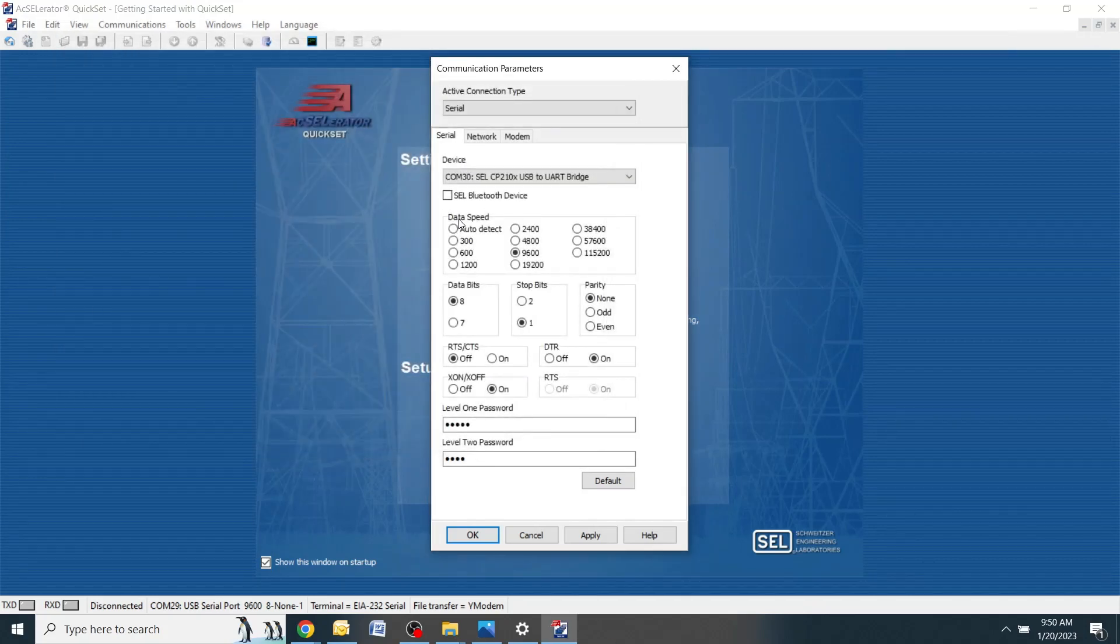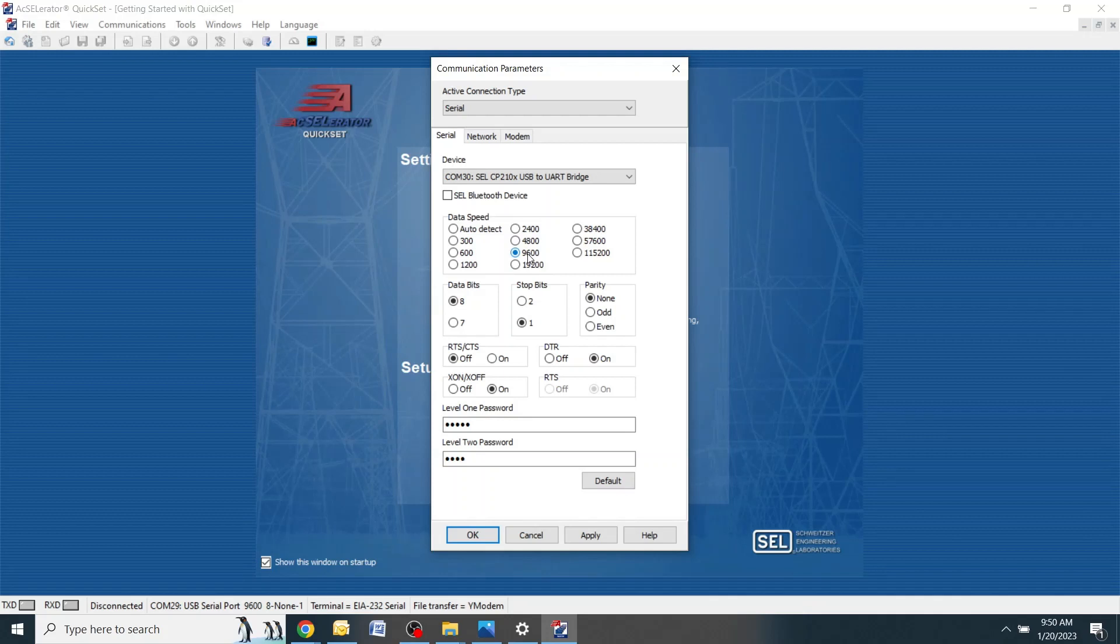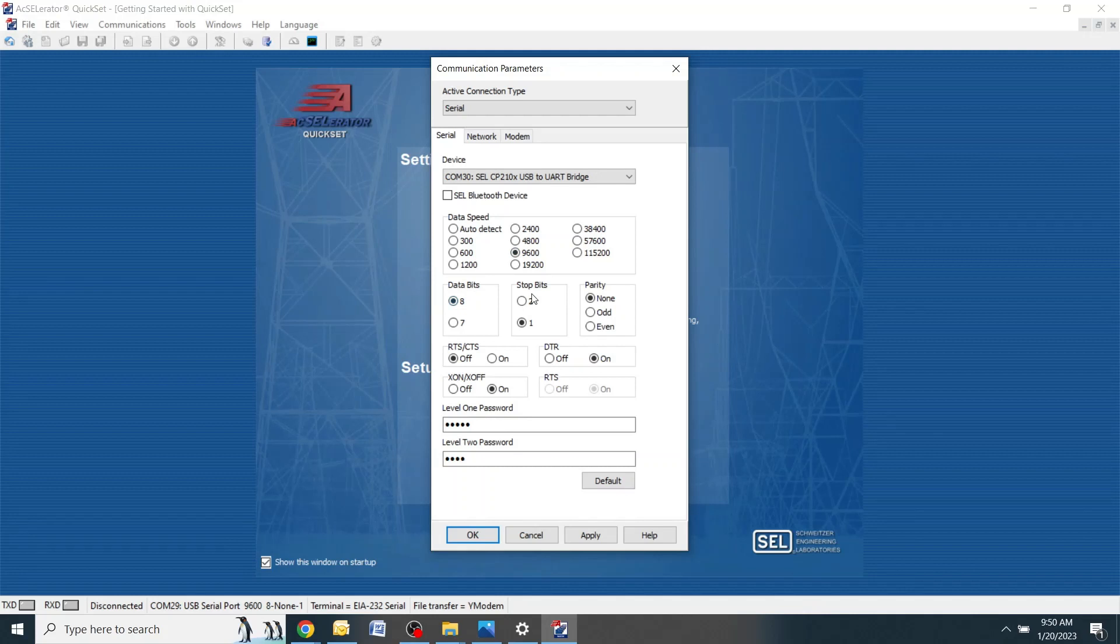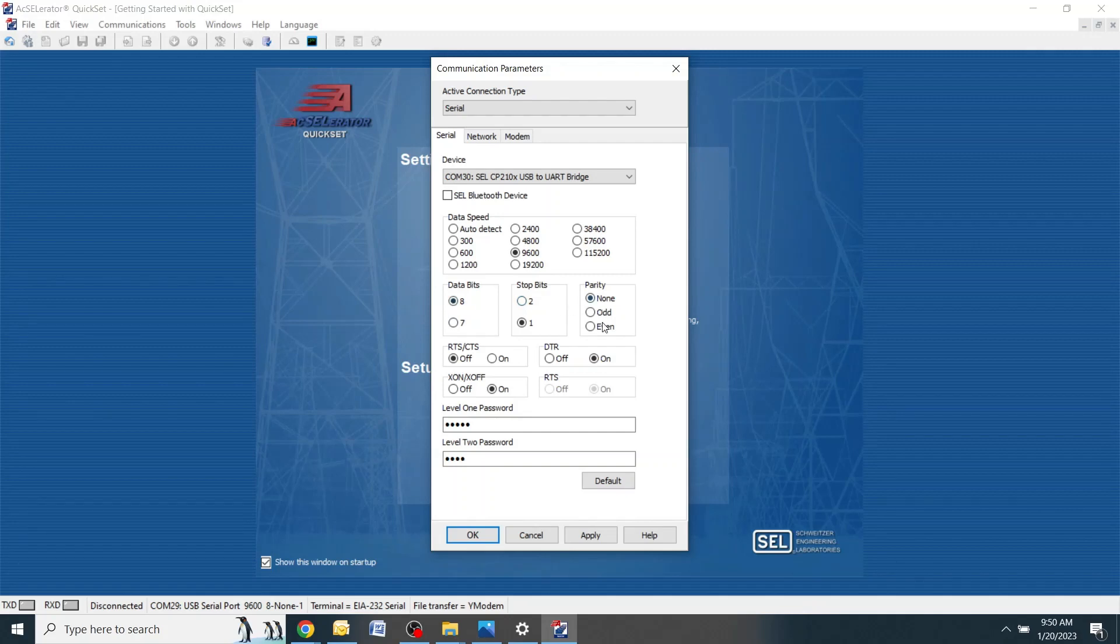Next, verify that the data speed is correct. This should match the baud rate that you looked at on the front of the relay when you were in the port F settings. The data bits, stop bits, and parity, a lot of these will be defaulted to the correct settings but always check and make sure that all that's right. If all these parameters are correct, click OK.